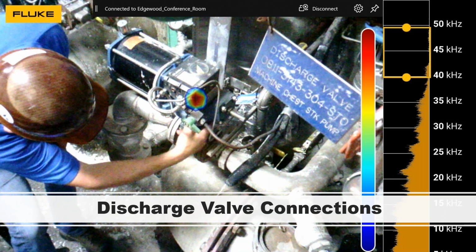Take a look at this really fast and look at all that noise down there below 20 kilohertz. That's the stuff we hear. That's compressor noise, machine noise. That chart gives you frequency versus decibel level. Down there, you're talking 70, 80 decibels of auditory noise in that area, where you would want to be wearing earplugs, and you can't hear a hiss even right up close to it, there's too much. But you can find a range that works for this that finds that leak.